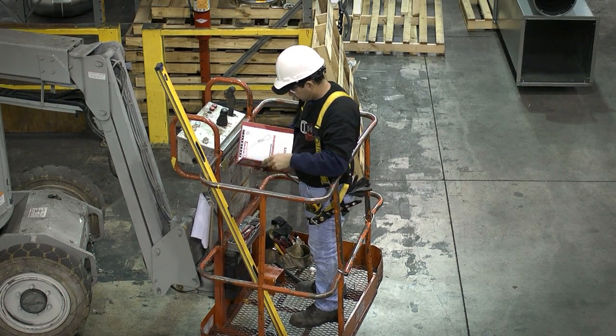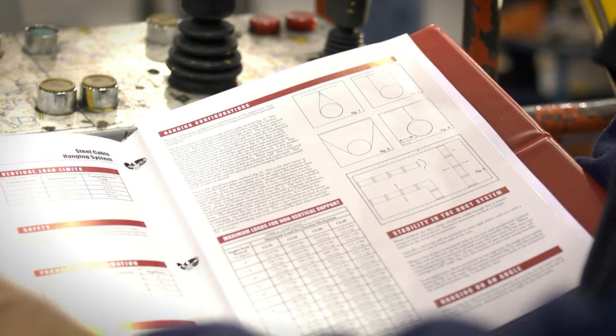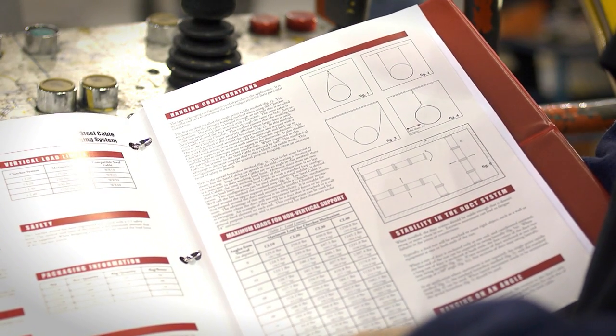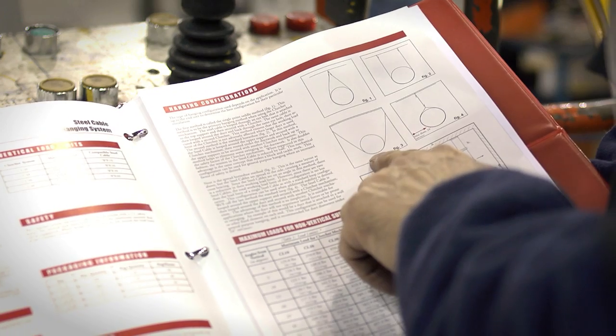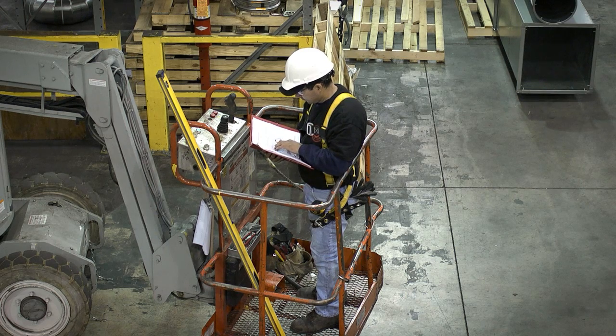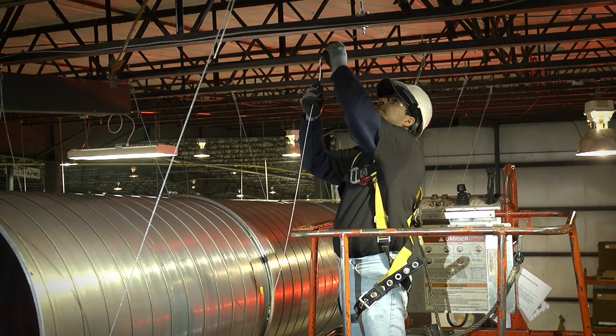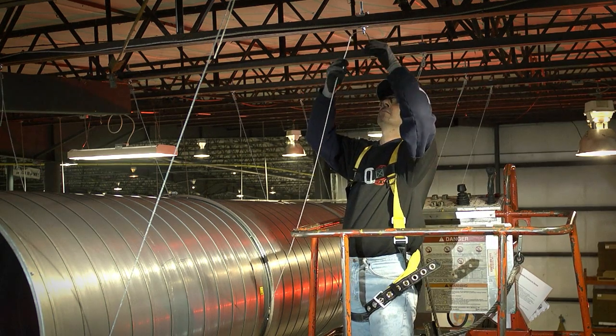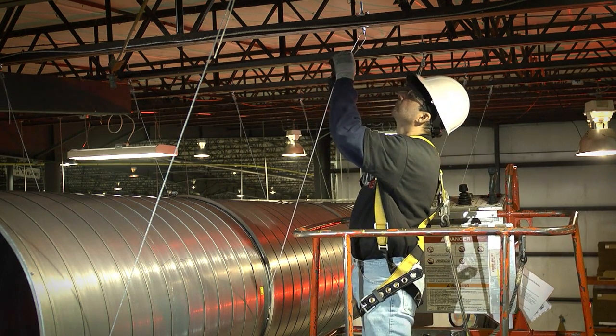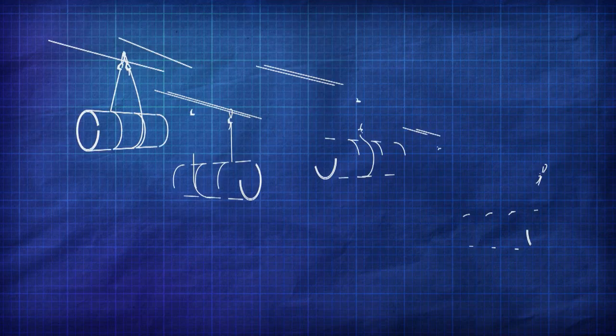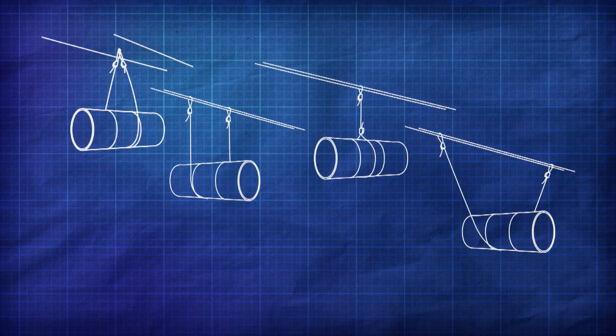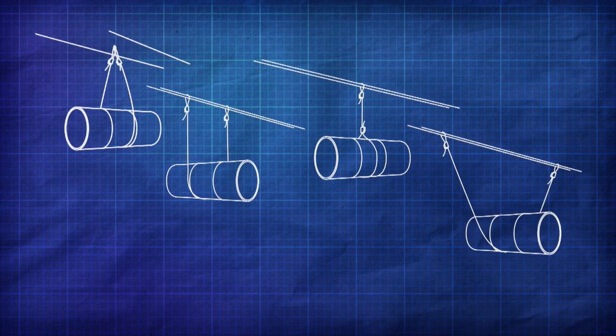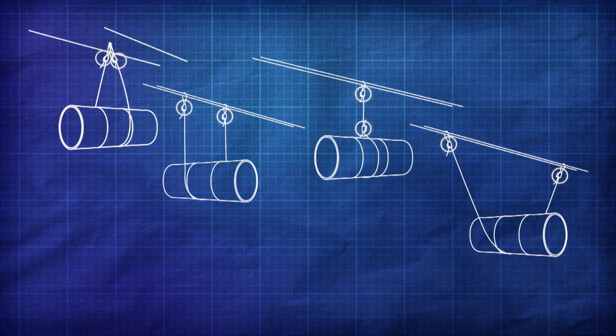Ductmate recommends using one of 4 hanging configurations when using the clutcher system. Consider the amount of support the building structure provides. Then choose the appropriate configuration method that best ensures the prevention of lateral movement. Whichever specified system is decided upon, it should always be fitted with the appropriate number and size of clutchers.